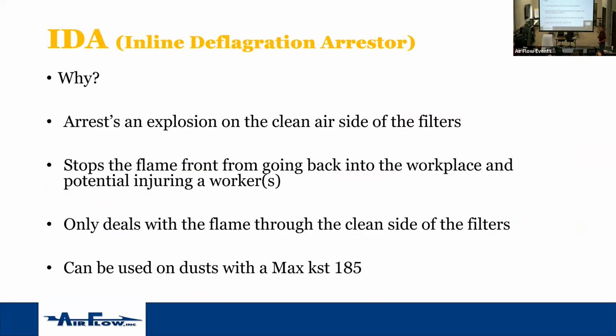IDA, what does the IDA do? Again, it arrests the explosion going through from the dirtier side to the cleaner side. It stops that flame front, so that flame front doesn't go back into the workplace, it doesn't go back into the building, it doesn't cause that secondary explosion when all that dust from the rattle happens. Again, it only deals with the flame, not the pressure ball going through it. And it is a max Kst of 185. So once you hit anything above 185, now you're dealing with a different method of controlling that deflagration going back into the space. That's a Vigiflap, that's an EIV, it's a fast-acting slide gate.